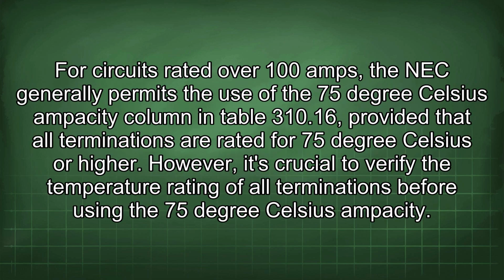For circuits rated over 100 amps, the NEC generally permits the use of the 75 degrees Celsius ampacity column in Table 310.16, provided that all terminations are rated for 75 degrees Celsius or higher. However, it's crucial to verify the temperature rating of all terminations before using the 75 degrees Celsius ampacity.